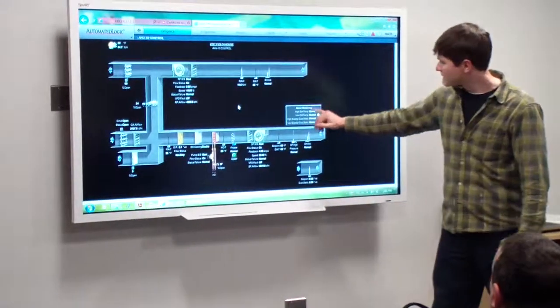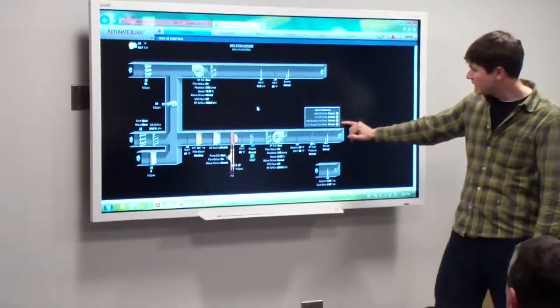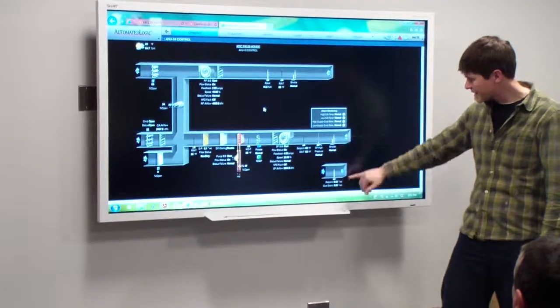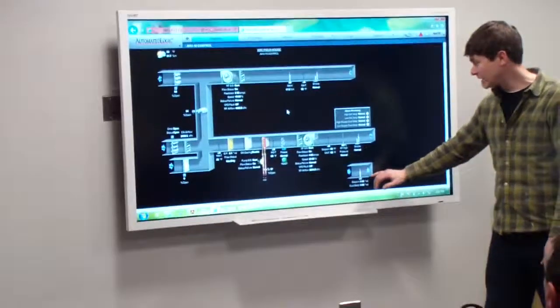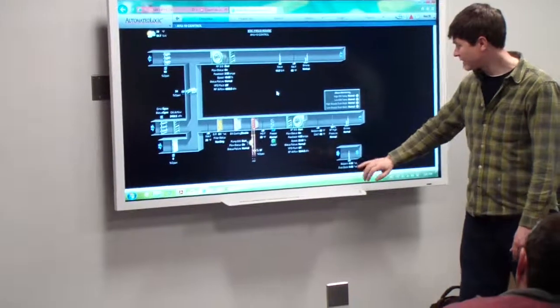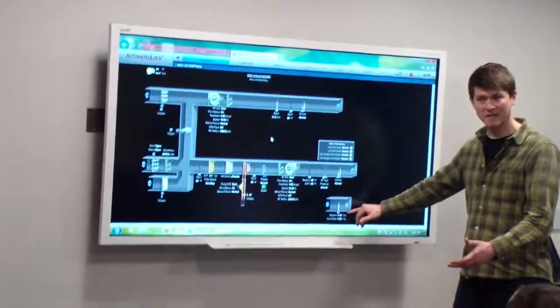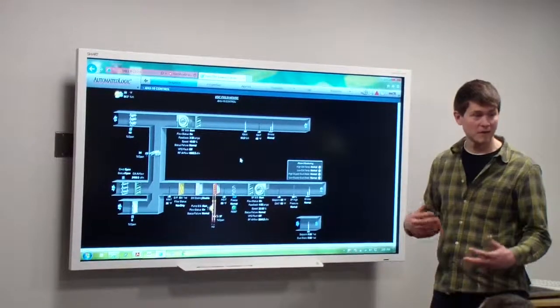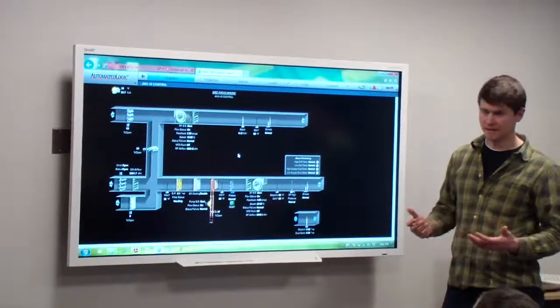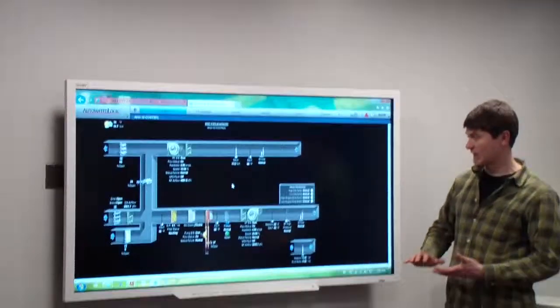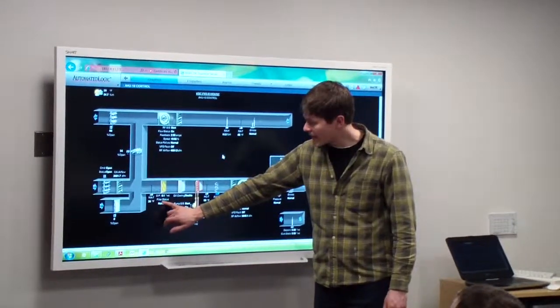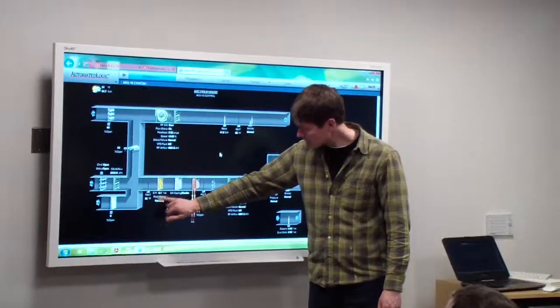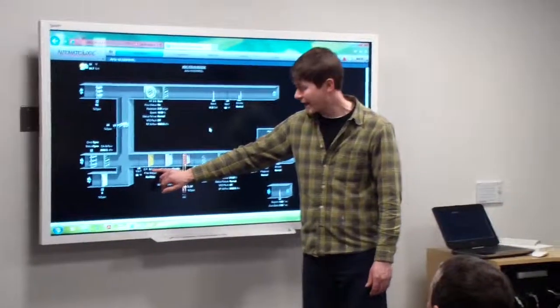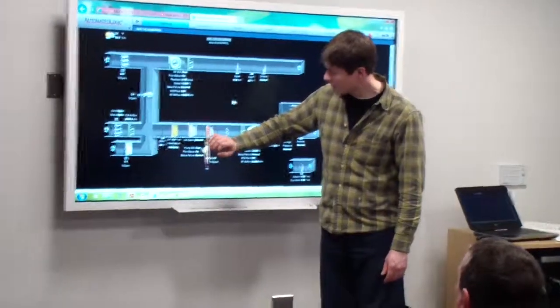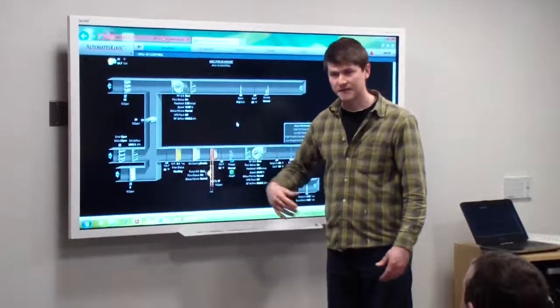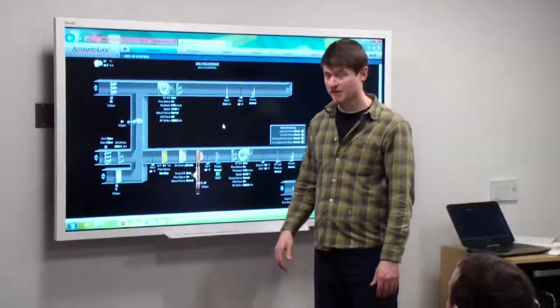And you also have a set of alarms here, which is high and low discharge air temp, high supply duct static, low supply duct static, which is this number here. So if the units start ramping way down and they're not supplying enough air over, I think it's over 10 minutes or so, they'll actually get an alarm back. You know, there's something going on with the VFDs, signals conflicting or something like that causing it to be low. You also have a dirty filter alarm. So as this starts to approach 1 inch, this will go gray, and then you'll actually start to get an alarm coming back saying, hey, it's time to change your filters.